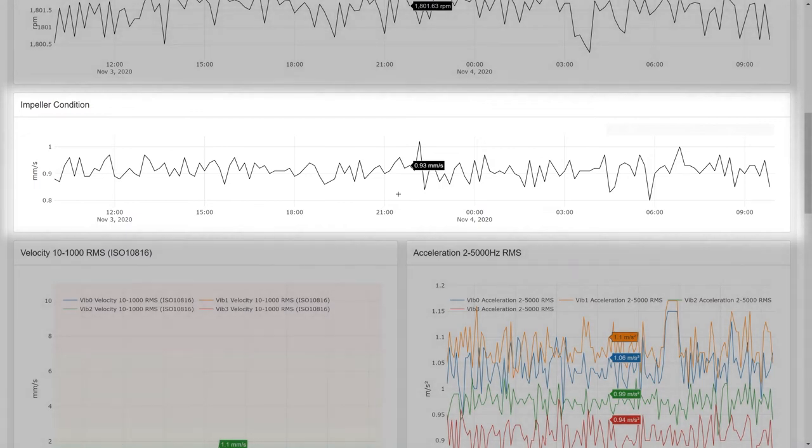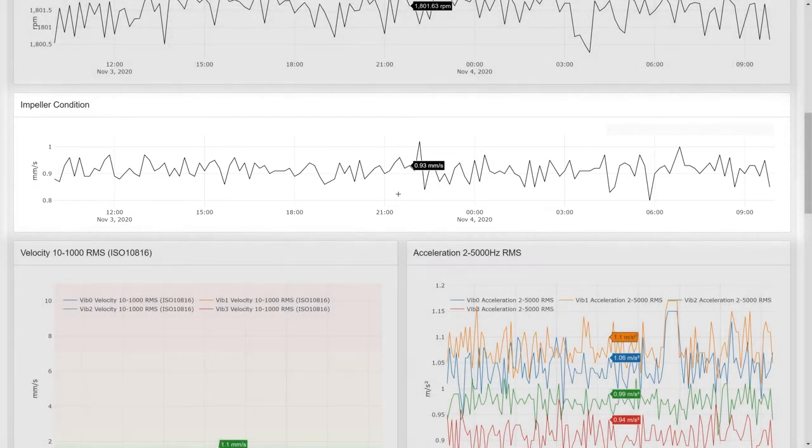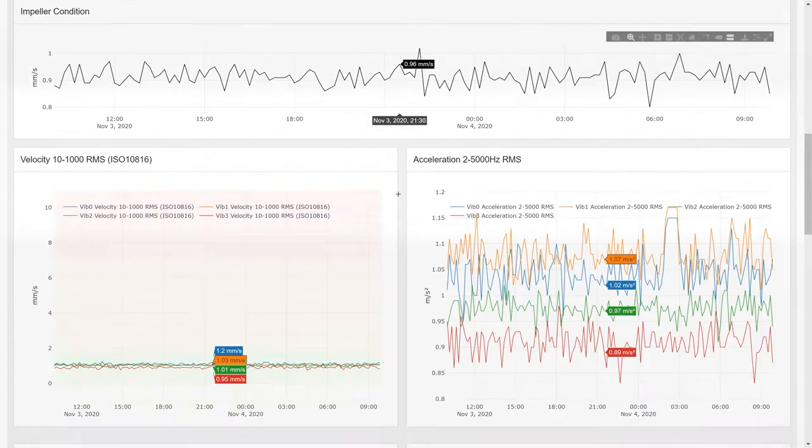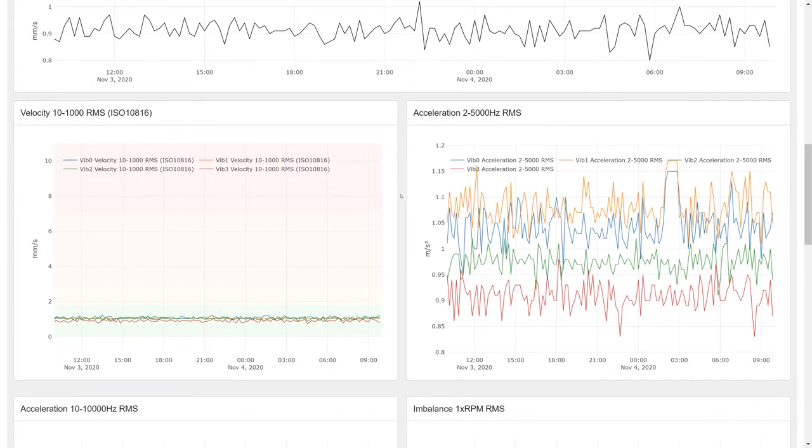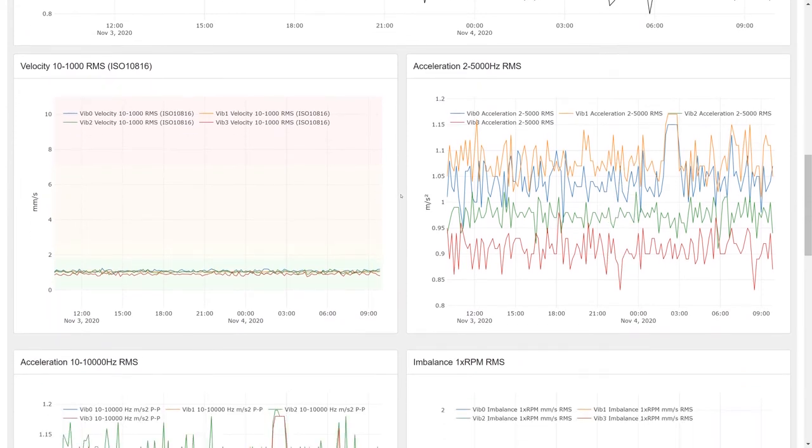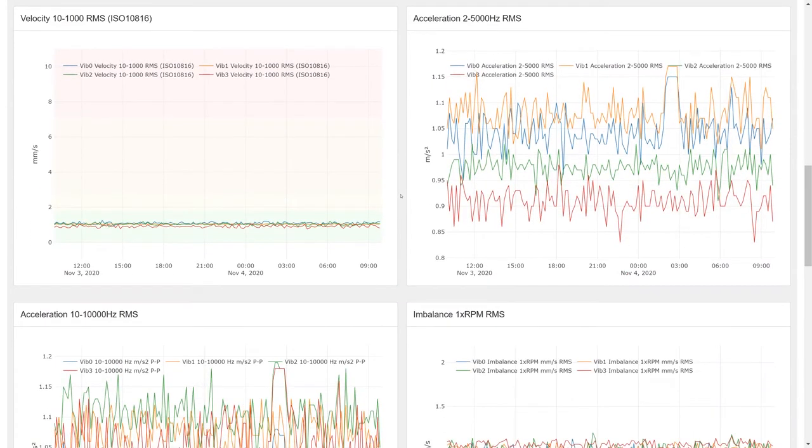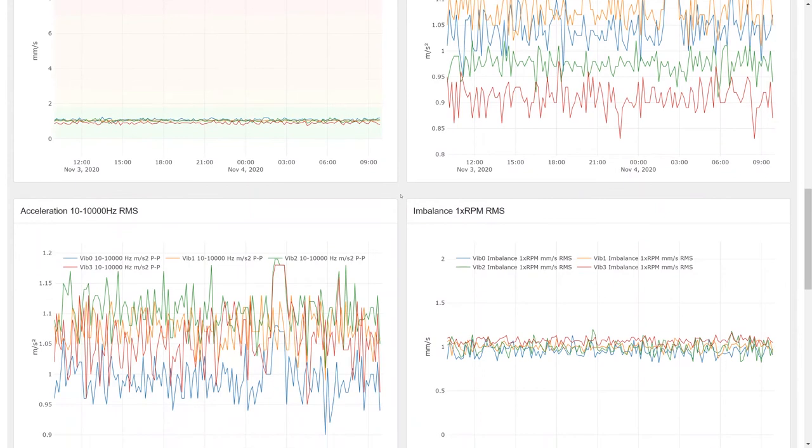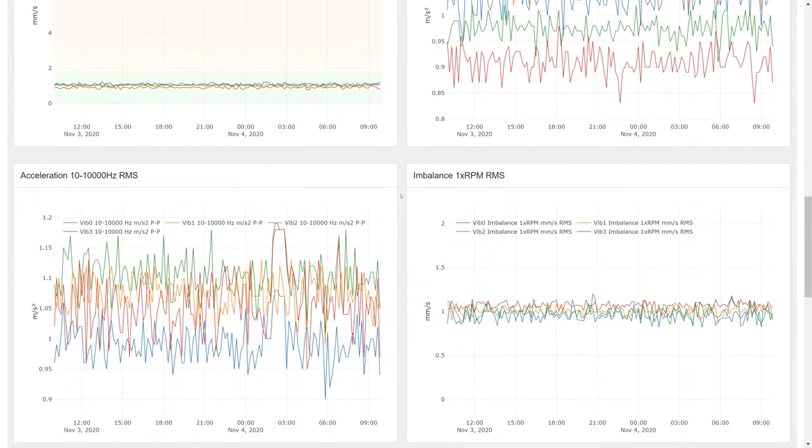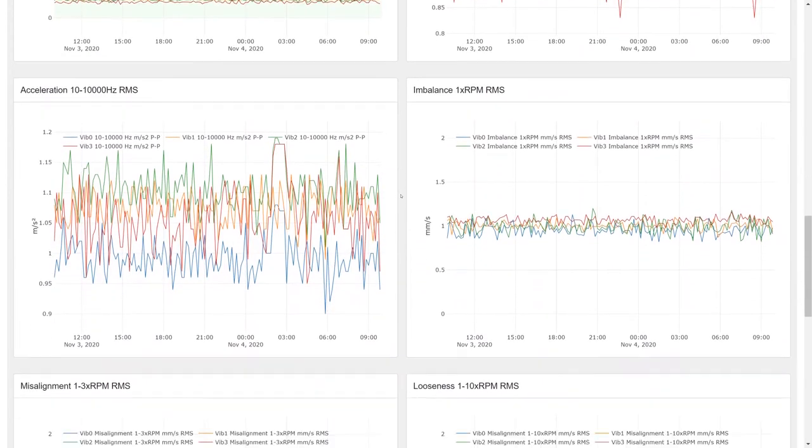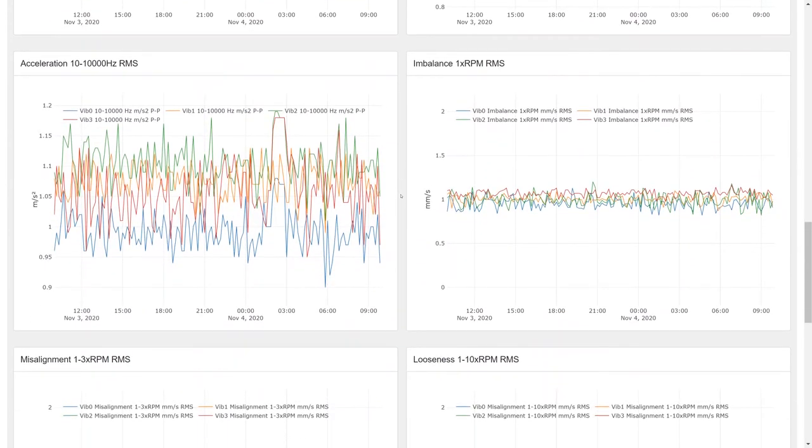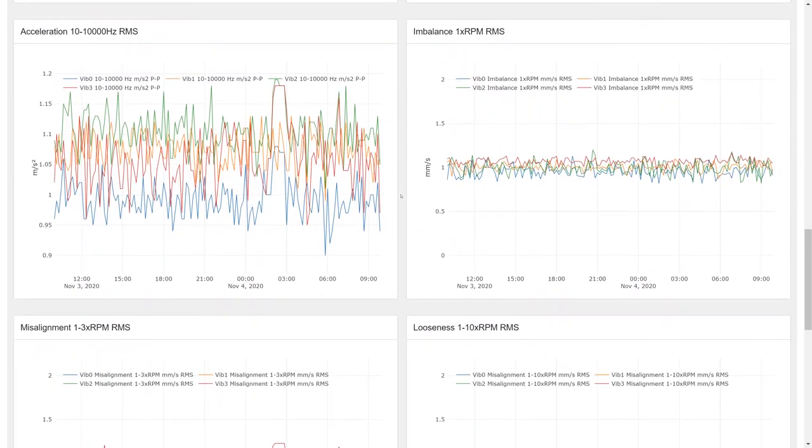On top of vane pass frequency, impeller fouling or damage is usually also seen as multiples of running speed. Fouling or deterioration typically generates imbalances and, therefore, dashboard includes these metrics as well.